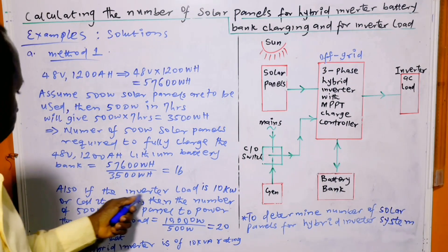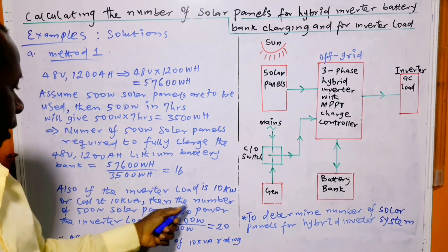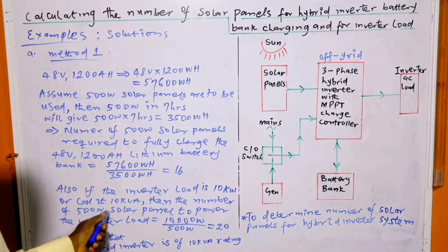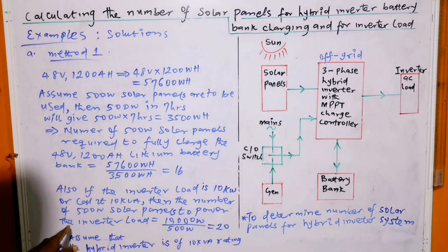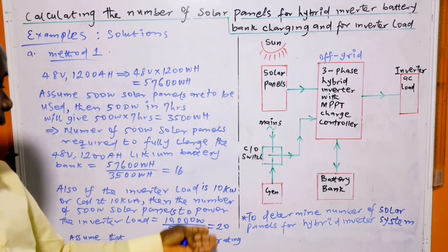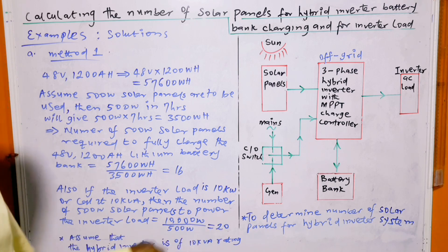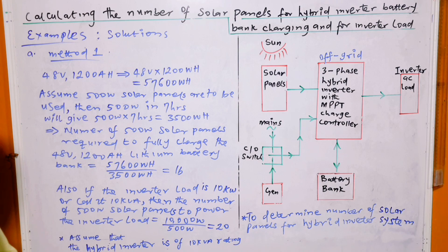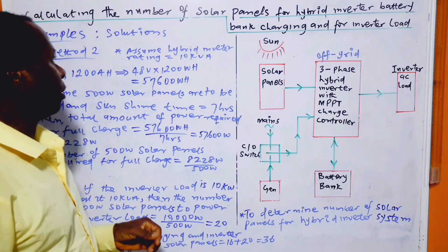Also, if the inverter load is 10 kilowatts (10 kVA), the number of 500-watt solar panels to power the inverter load will be equal to 10,000 watts divided by 500 watts, which gives us 20. So assuming the hybrid inverter itself is of 10 kVA rating, we need 20 panels for the load.